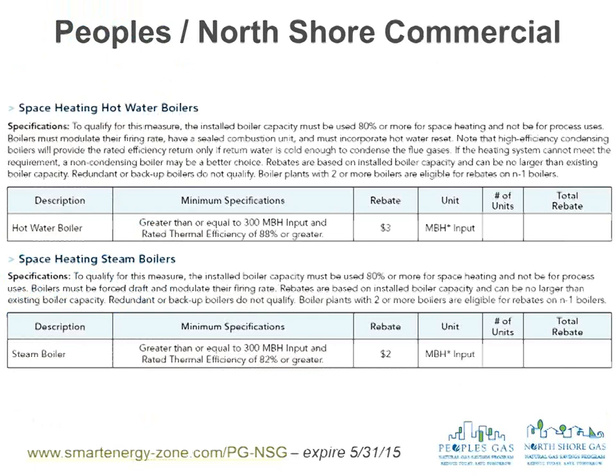All right, that brings us to North Shore and Peoples Gas. We'll talk about those combined because just like residential, they are the same program on the commercial side as well. There's a rebate for boilers that are 300,000 BTUs and larger. They got to be at least 88%, so they're basically condensing boilers. It is $3 per MBH. So if you put a 1 million BTU boiler in that's 90-some percent efficient, you get a $3,000 rebate.